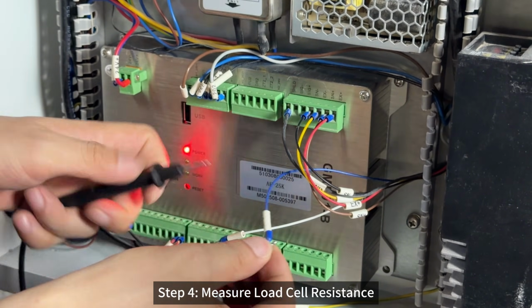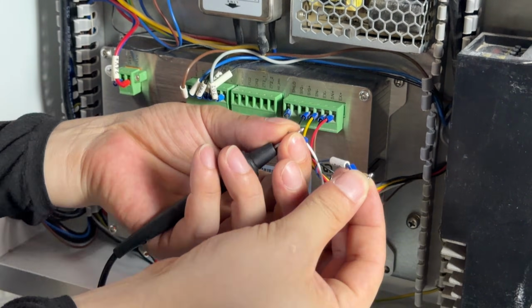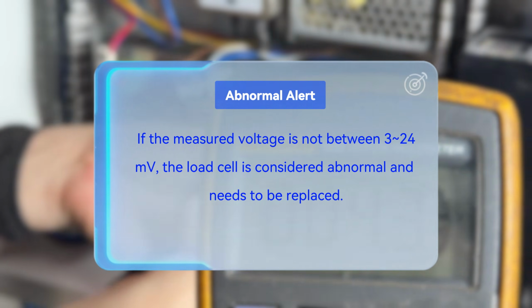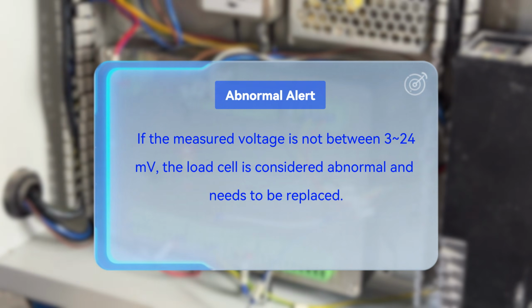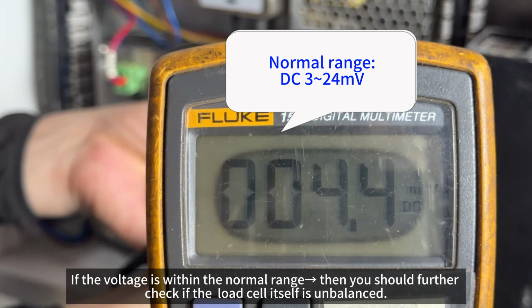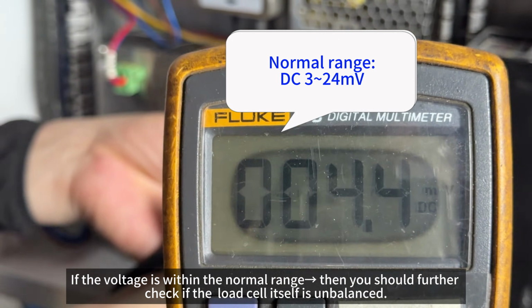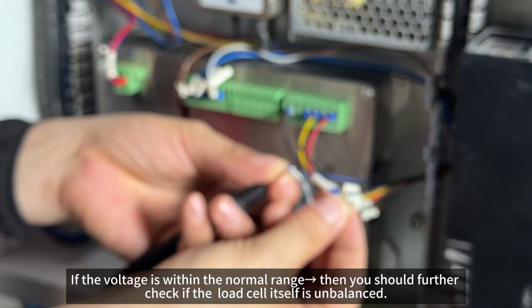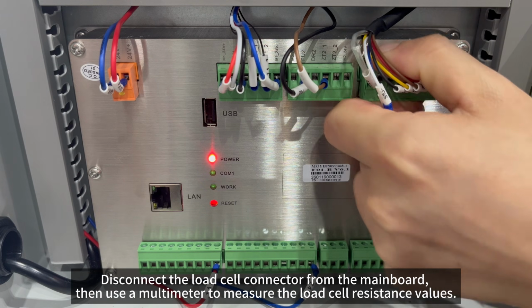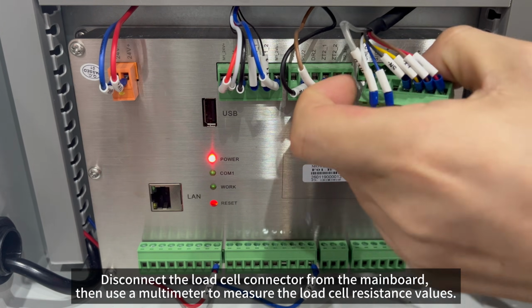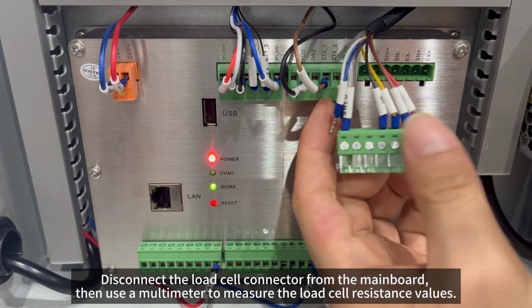Step 4. Measure load cell resistance. If the measured voltage is not between 3 to 24 mV, the load cell is considered abnormal and needs to be replaced. If the voltage is within the normal range, then you should further check if the load cell itself is unbalanced. Disconnect the load cell connector from the mainboard, then use a multimeter to measure the load cell resistance values.